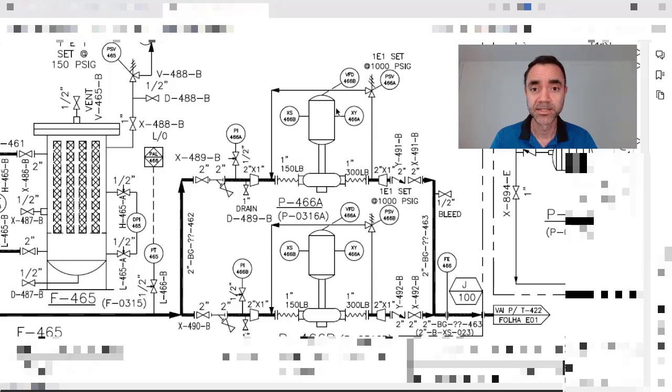Based on the needs of the process, it can have a higher rotation or lower rotation, and with that regulate the flow that is required by the process. For maintenance purposes, I also have an isolation valve in the discharge, and I have also a check valve to prevent the misdirection of flow going to the pump.